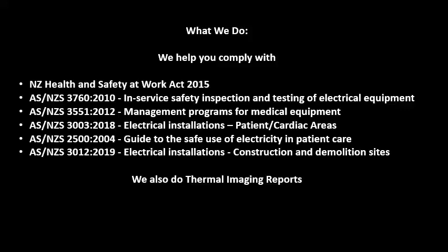As a company, we've recently stepped into thermal imaging reporting, which allows us to check server rooms, power outlets, and heavy machinery that's permanently wired. This is a non-contact inspection that helps us find faults that may lead to fire or electrical breakdown within a company environment. We've seen recently a school go up in flames because of an electrical fault, so thermal imaging goes a long way toward spotting issues in a wiring area that may need further inspection by an electrician.